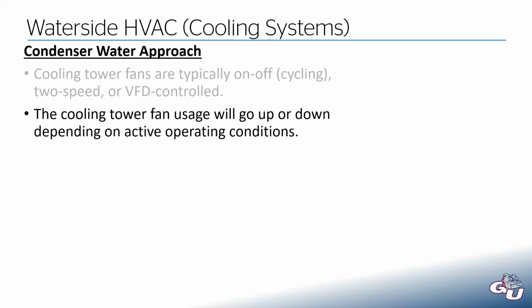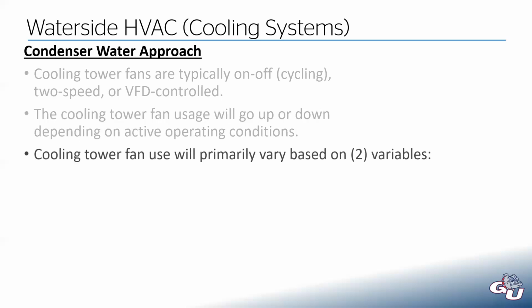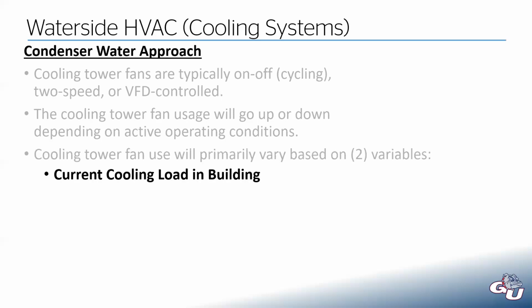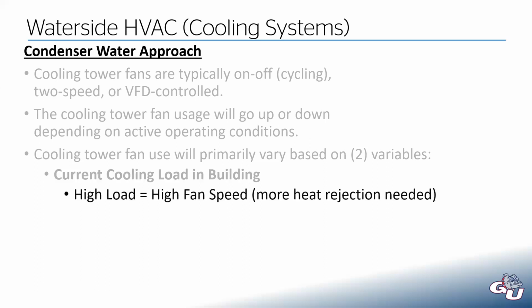Our cooling tower fan usage. So how much energy that fan is going to use is going to depend on our active operating conditions, which really comes down to two primary variables. We're going to have our current cooling load in the building. So if we have a high load, if we need a lot of cooling, that will lead to a high fan speed because we need more heat rejection.